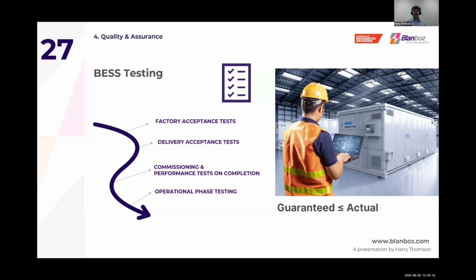Lastly, we have the operational phase testing. This is quite similar to the performance test previously mentioned, but this occurs typically on the anniversary of the test on completion. Again, you'll be measuring the energy capacity, round-trip efficiency, and also the availability of the BESS project in the previous year. This is important as it gives insight into the degradation of the battery, and it also allows you to optimize maintenance to prevent unexpected failures down the line.